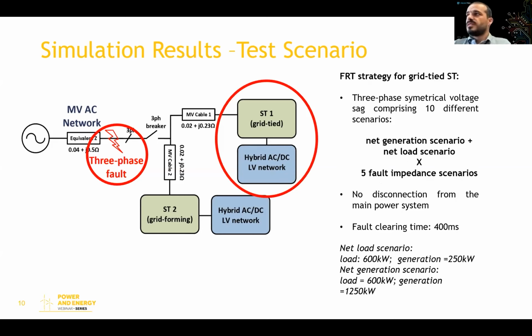To evaluate the fault ride-through strategy for the grid-tied smart transformer, 10 scenarios are considered: a net generation scenario and a net load scenario, each one with 5 fault impedance scenarios. At first, there is no disconnection from the main power system, and the fault clearing time is 400 milliseconds.